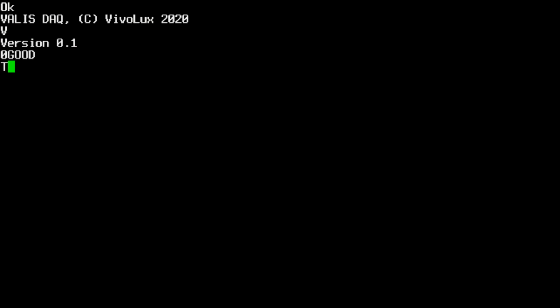So here I have a serial port open connected to the DAQ, so we will take that a reset. I'll print the message. So we'll try sending a basic command, the V. It will let us know what version it is. We can set the timer speed by doing T and then a 16-bit number, so we can do 05CF, and it'll let us know it's good. If we send a malformed command, so say we send too many characters, it'll let us know that we have a bad parameter. If we try and send a command that doesn't exist, it will say it's a bad command.